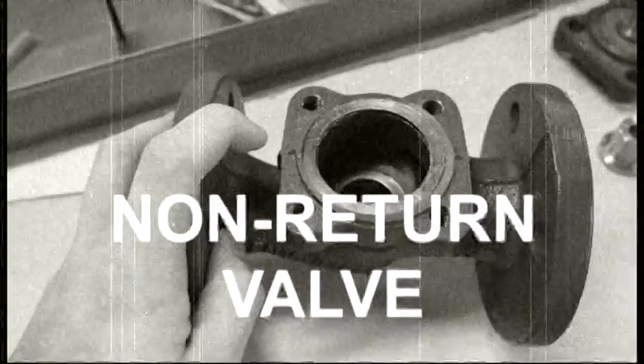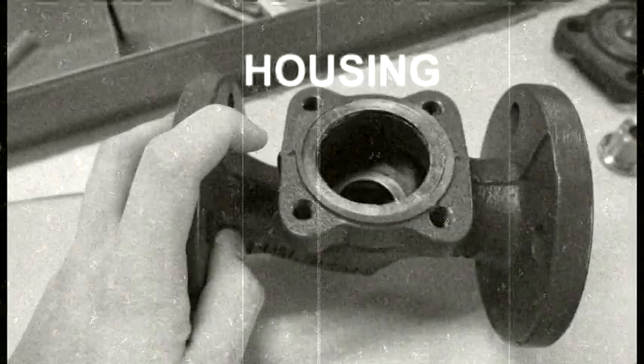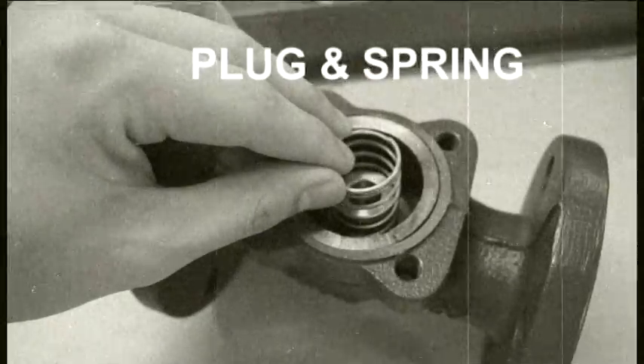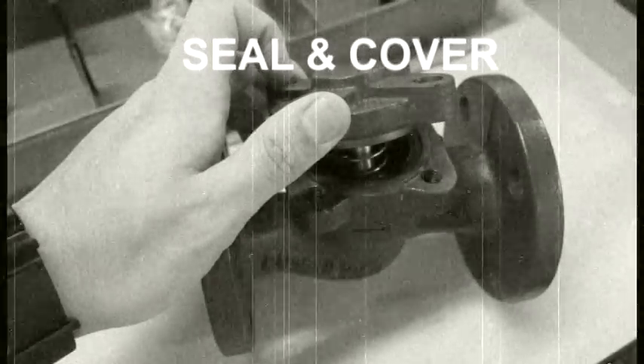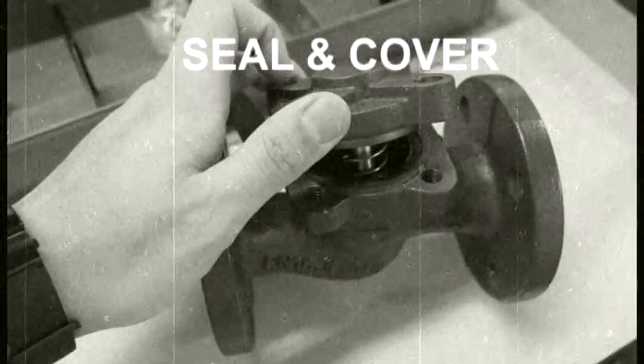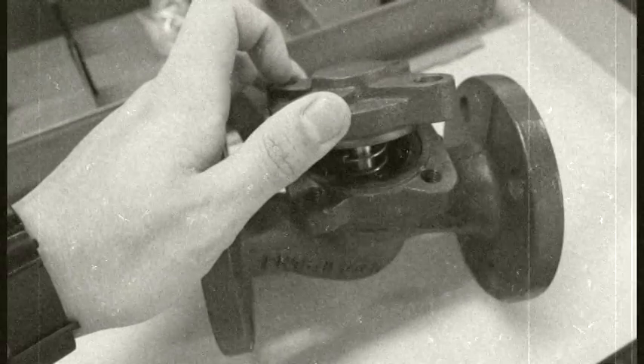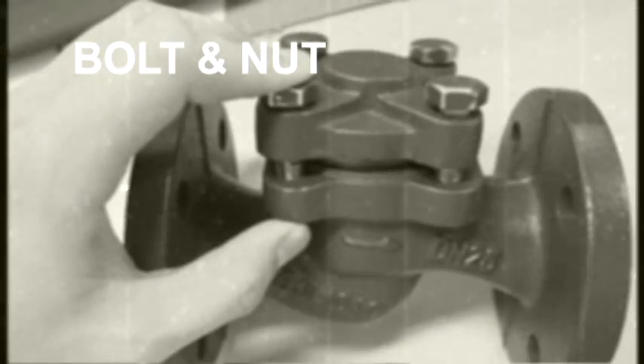For the non-return valve, we first place the valve head into the housing. The spring is then fitted around the valve head. A seal is placed on top and then a cover is placed on top, without moving anything as much as possible. Then the cover is locked using hexagonal screws. Isn't it simple?